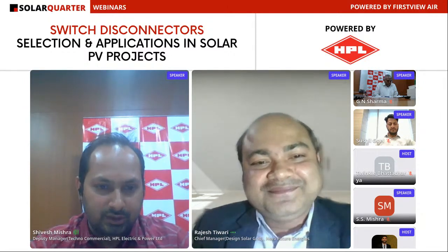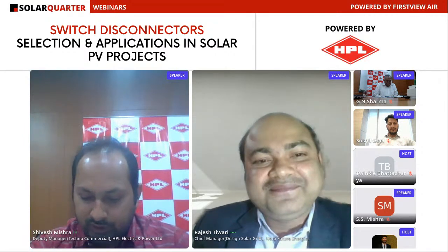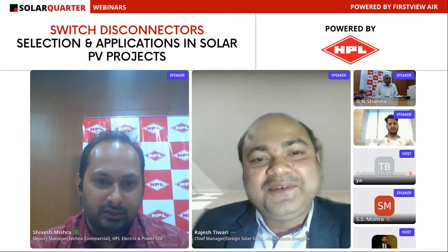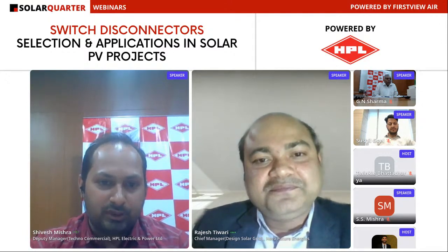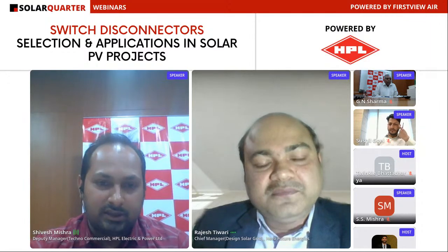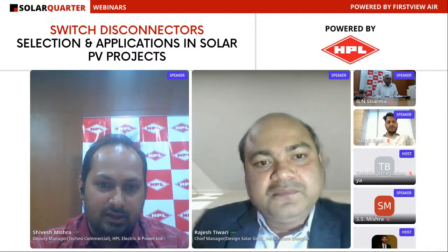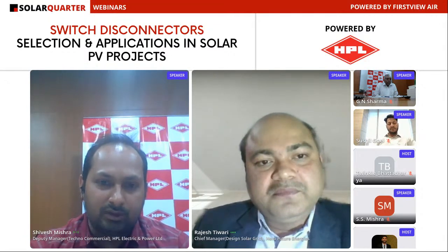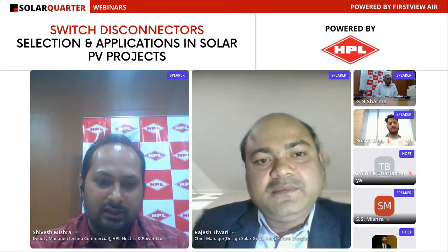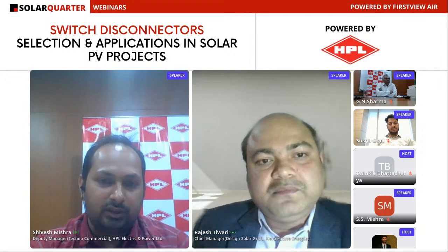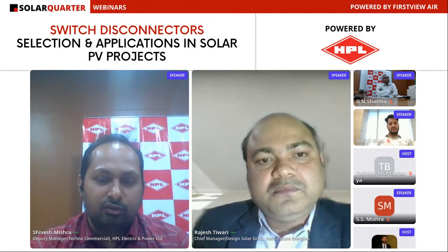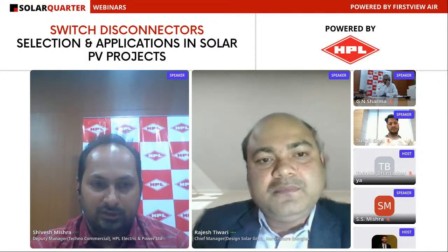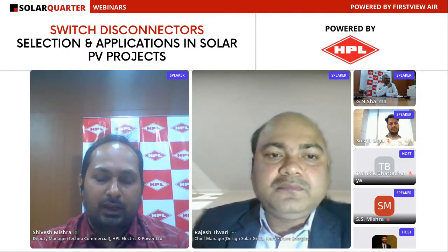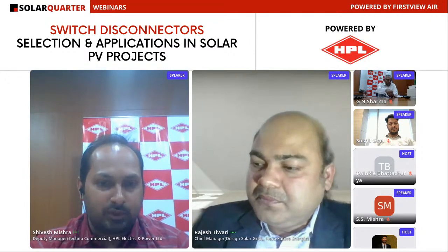Thank you very much, sir, for the information and guidelines. Coming to the point about the temperature which we maintain, the testing facility: all the solar products which we manufacture at our facility, either SCBs or SMBs, we have a temperature rise testing facility in house, where we have a chamber in which we maintain an ambient temperature of 50 degrees. In that condition we maintain the site condition as per the ambient we get from the RFQs and the design we get from the developer or IPP side. Sometimes it is 45 degrees, but mostly it is 50 degrees.